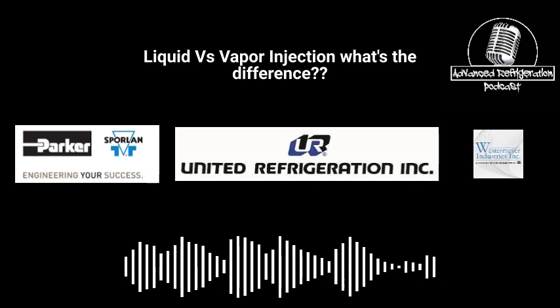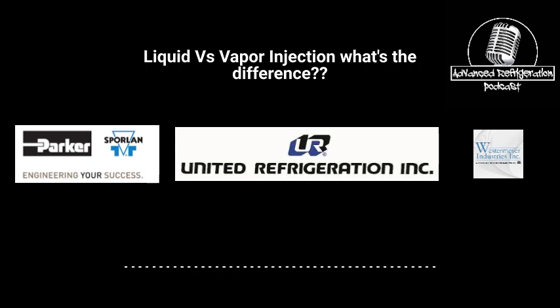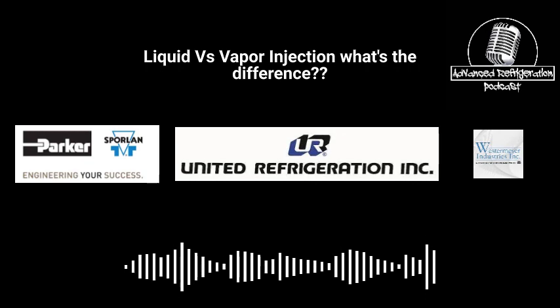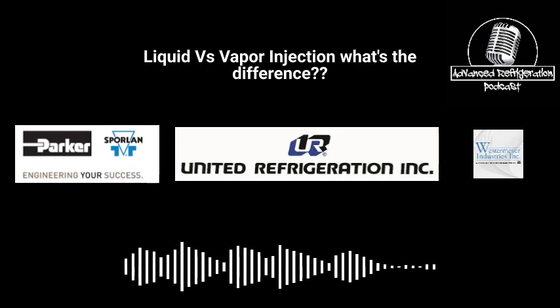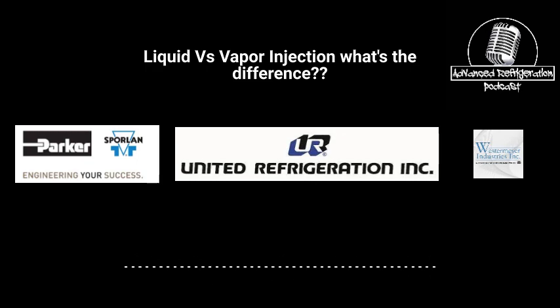Then as the subcooler temperature starts coming back up and it wants to kick on that solenoid, now you potentially have this huge electronic expansion valve that's wide open and about to start beating the hell out of your last stage head, killing your valve plate.